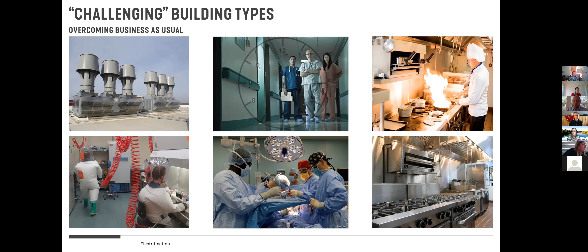So this is a building that is approximately half wet chemistry and half classroom. As you can see, it's a 5-story project. So again, from a height limit, it's a good sized project. And wet chemistry tends to be one of the more complex project types to electrify, especially because of the amount of air changes that are being driven by that hood exhaust.